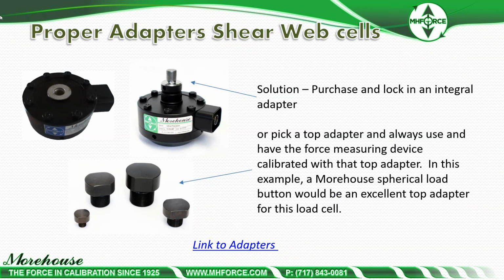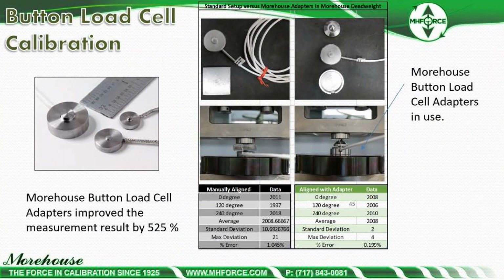Shear webs. Remember I said about the hole? Any load cell with a hole, this hole right here, any load cell with this type of hole should be suspect. It's not good. If it's sent in without adapters, it's just simply not good. So our solution, because you have that thread depth problem, our solution is to purchase and lock in an integral adapter. If that cannot be done, secondary solution is pick a top adapter and always have it in the force measuring device. For tension, same thing. Send in a rod with a bolt on it. I mean, this is really where you're at. Button load cells. Morehouse button load cell adapters. Here's what most people use.